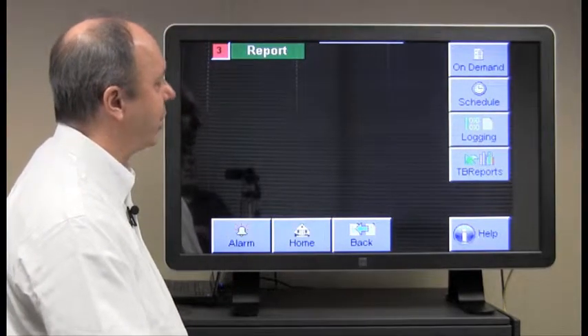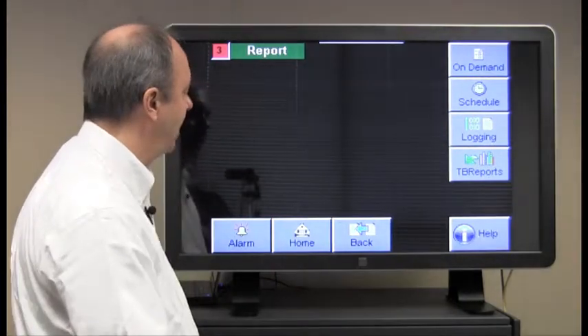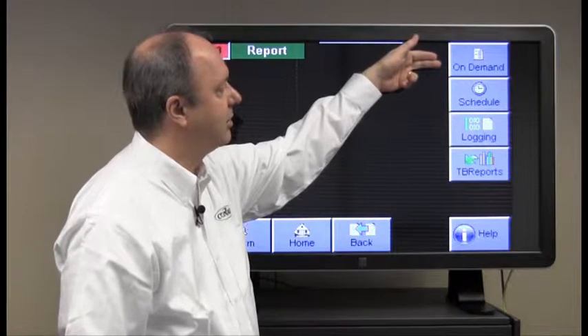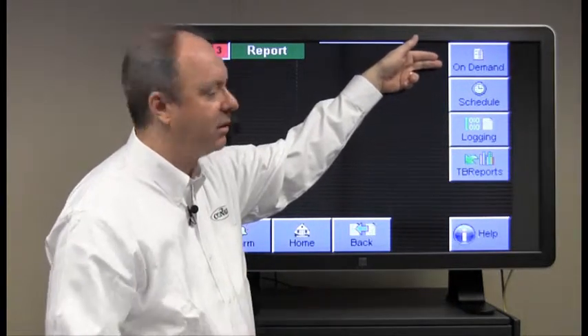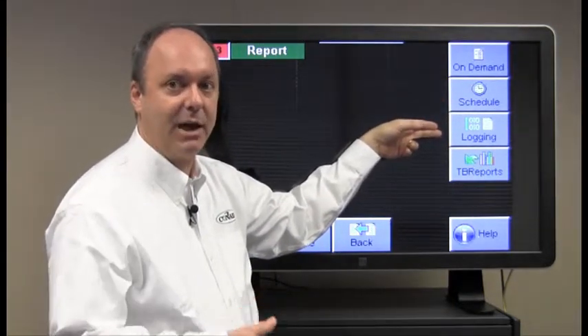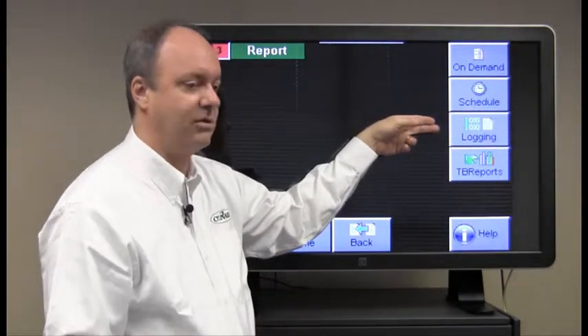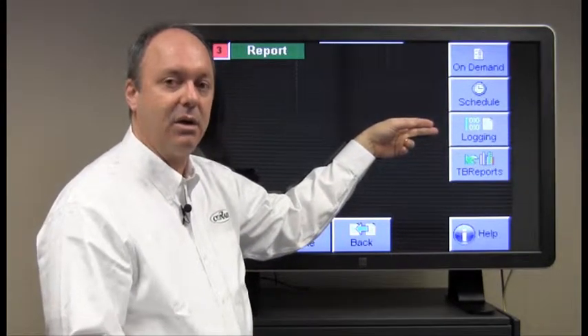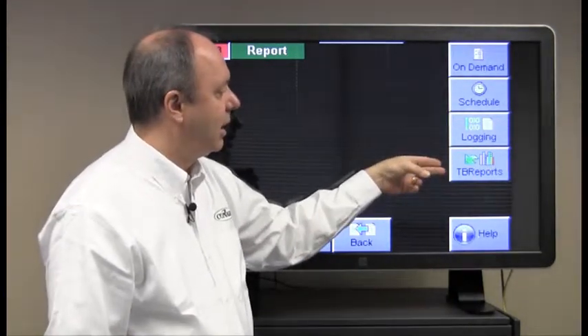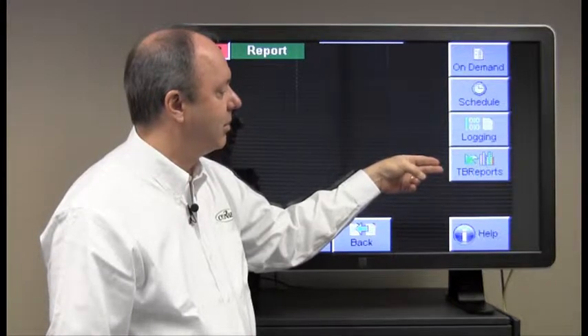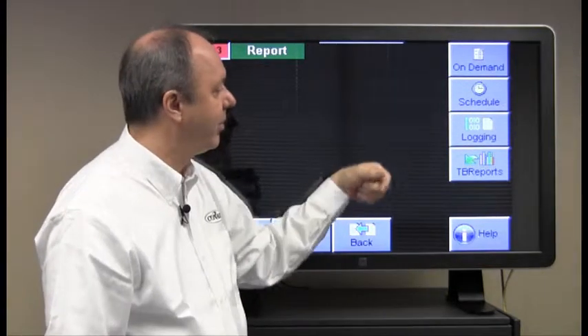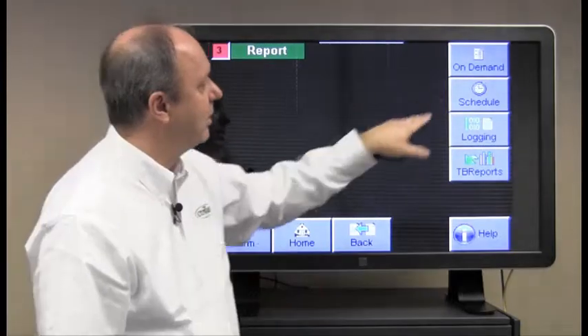We have four different methods for creating reports. The first one is on demand, which allows us to generate a report immediately. The second one is to schedule a report. The third one is to log data about the batch blender to a destination, such as a compact flash card located in the blender, or a USB thumb drive that you can plug into the blender. And the fourth method is to create reports out to a software package called TrueBlend Reports, created by Conair.